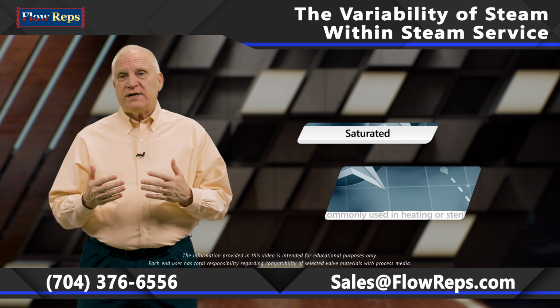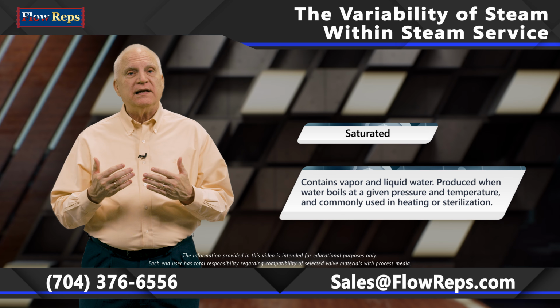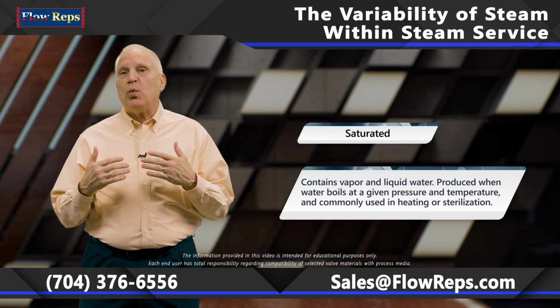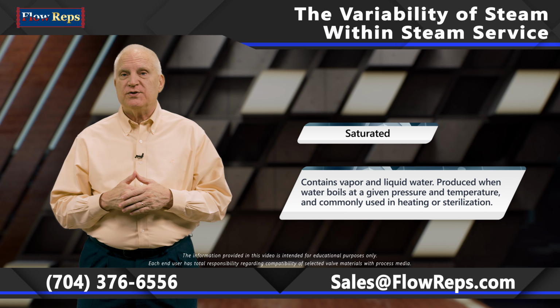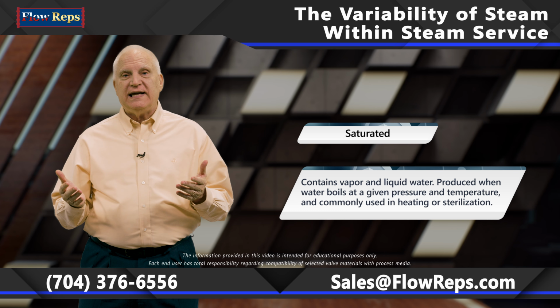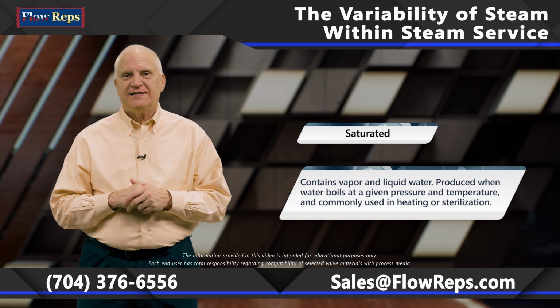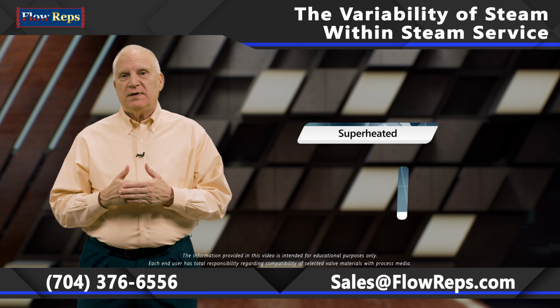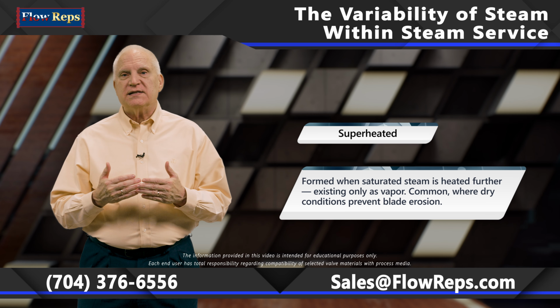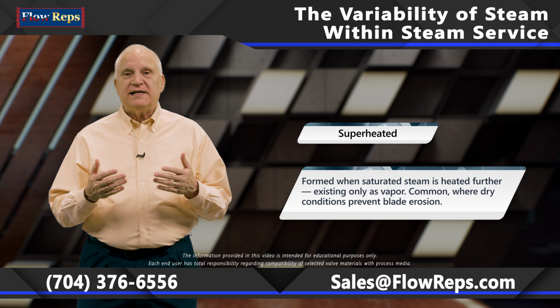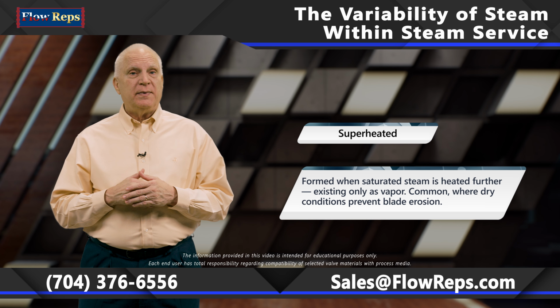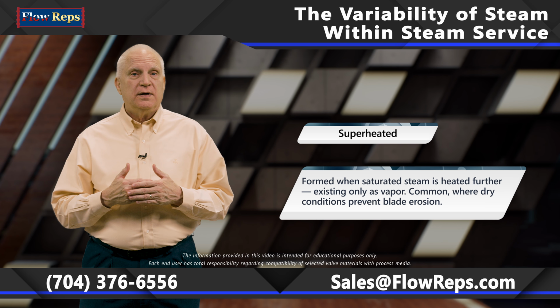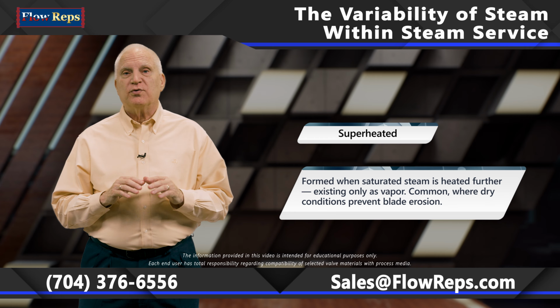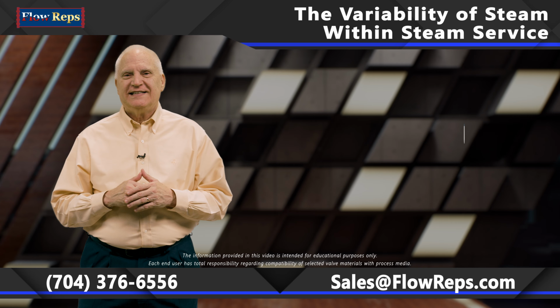First, saturated steam contains both vapor and liquid water. It's produced when water boils at a given pressure and temperature, and it's commonly used in heating or sterilization processes. Superheated steam is formed when saturated steam is heated even further, existing only as vapor and common in power plants and turbines, particularly where dry conditions prevent blade erosion.